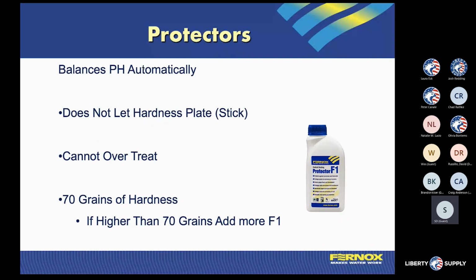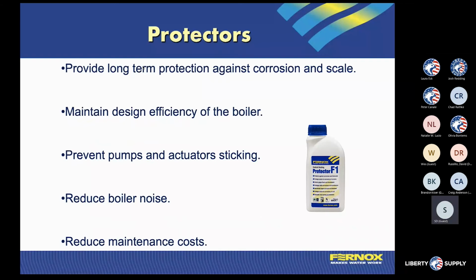We do work up to 70 grains of hardness. If we are higher than 70 grains, then we can add more F1 to buffer it down. Again, you're going to do some testing on the post side if you are at that level. In our market we don't see that very often, but it does come up once in a while. So I want to make sure that we talked about that. Obviously this is going to give us our protection against any more buildup. Like I mentioned earlier, if we just put inhibitor in, and we don't flush, we don't clean, we don't do anything else, we're going to stop the system from getting worse, but we're not going to deal with any of the existing problems with any kind of the scale, the hardness that's in the system.